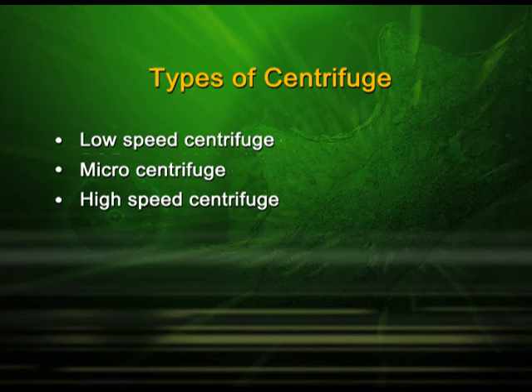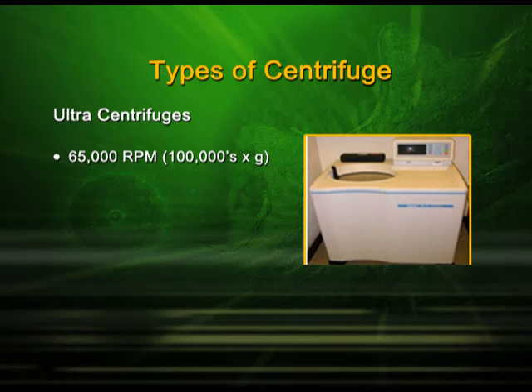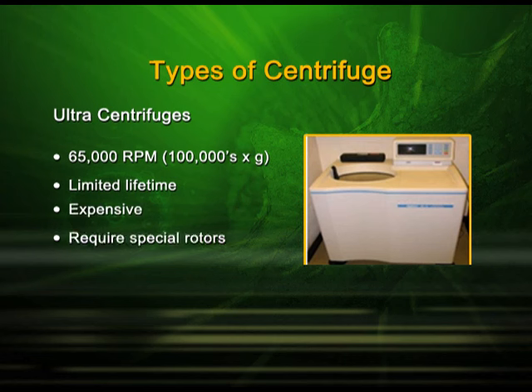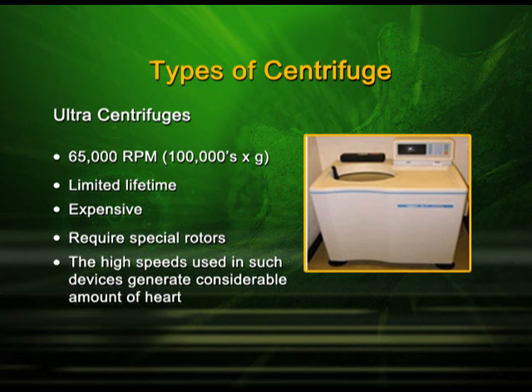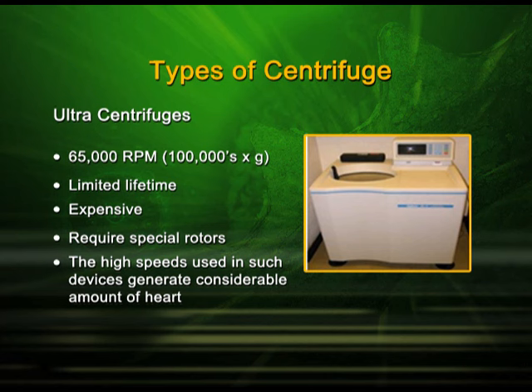The last type of centrifuge is the ultra centrifuge. It was discovered by Theodor Svedberg and runs at a very high RPM of around 65,000. It has a limited lifetime, is very expensive, and requires a special rotor. Because it runs at very high speed, excess heat is generated, and therefore a cooling arrangement is also required.